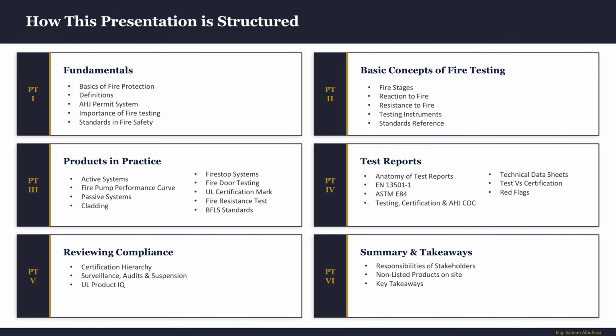And part 3 takes everything from part 1 and 2 and integrates them into the product itself. For example, the sprinklers, the fire doors, the cladding, the fire pumps, real products and the real requirements. And part 4 is test reports. This is where most people have gaps. You will learn how to read a fire test report and what makes it valid and what does it require, and certain red flags in the test reports.